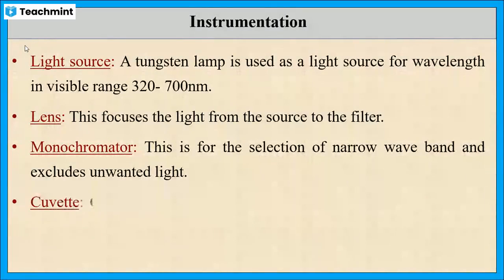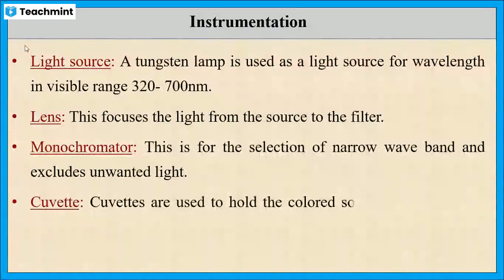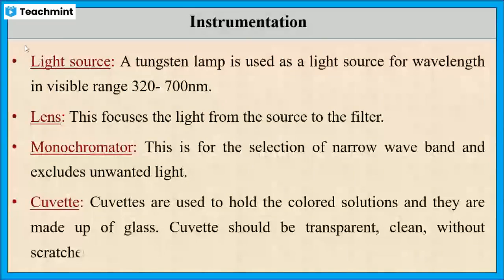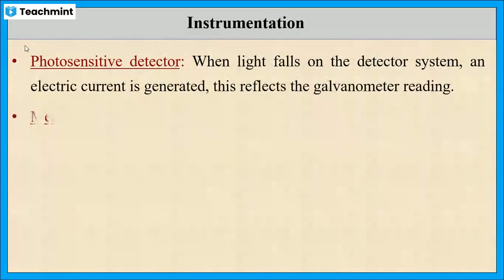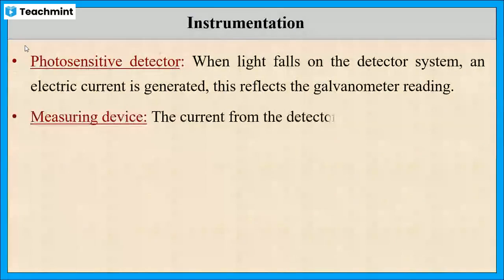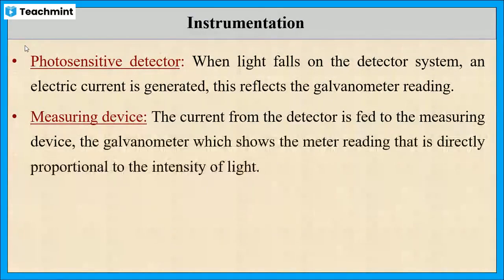A sample holder, or cuvette, is used to hold the colored solution. The cuvette should be transparent, clean, and without scratches. The photodetector converts the emitted light into an electrical signal, which is measured using a galvanometer and amplified in the amplifier.